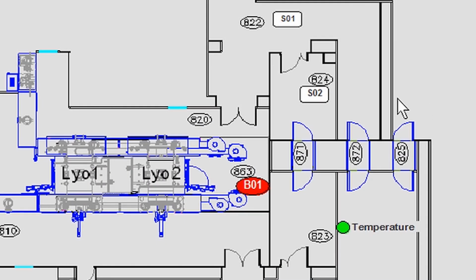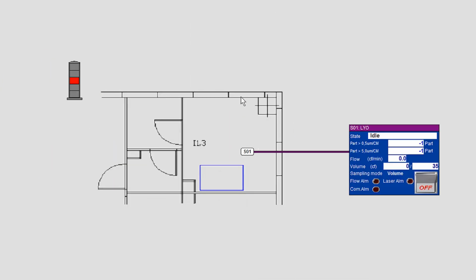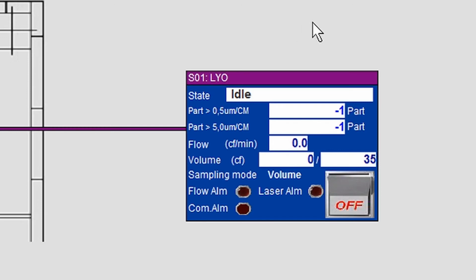To get a closer look at a particular section of the facility map, simply click to get an expanded view of that area. Once in that area, the specific sensor data is displayed. This information can include the sensor state, the readings for that sensor, in this case, the particle counts for 0.5 and 5 micron particles. Also noted is if the sensor is in alarm or has a failure. Additionally, with this particular sensor, there is the display for the local light tower tied to the monitoring alarms.